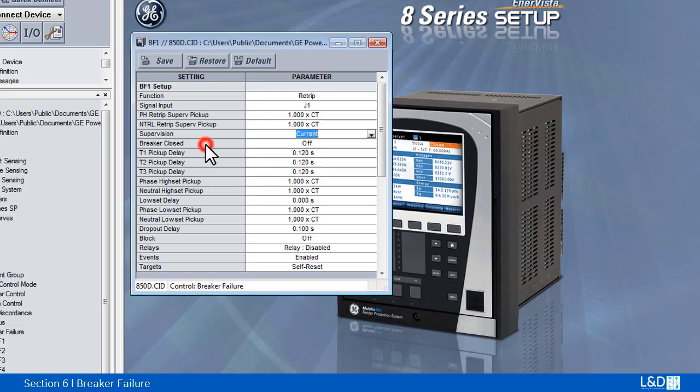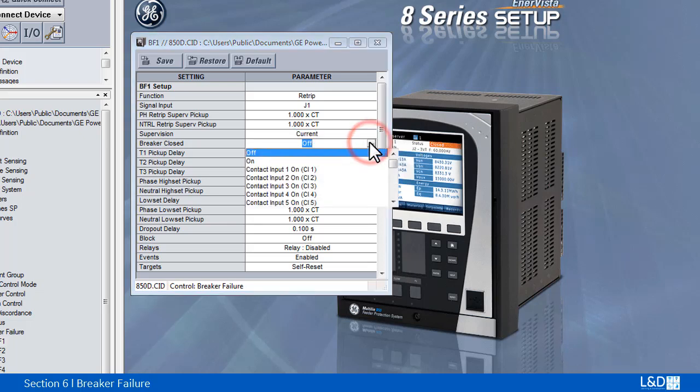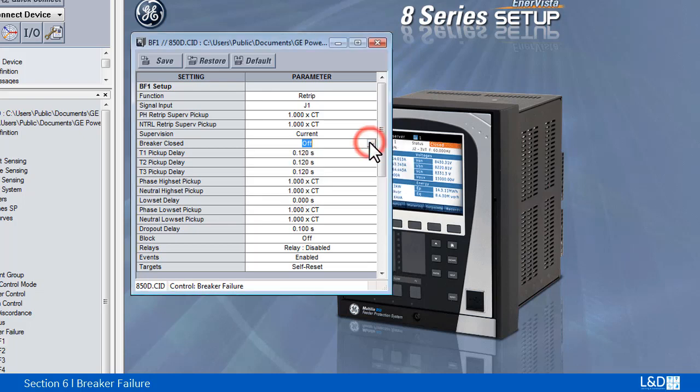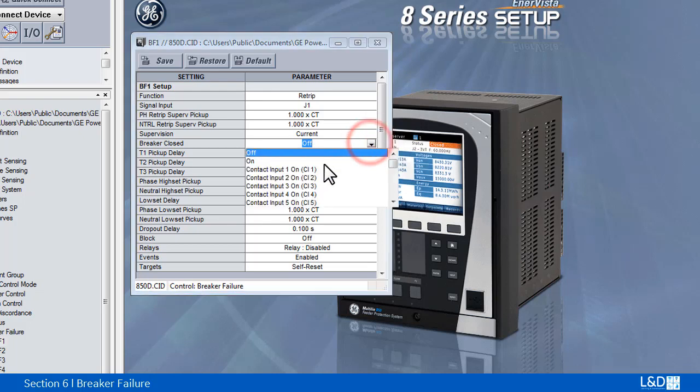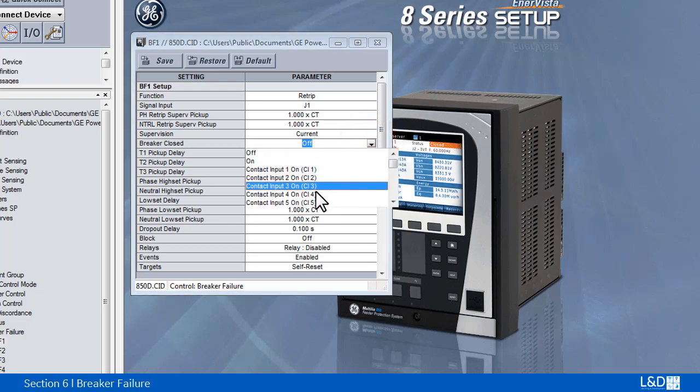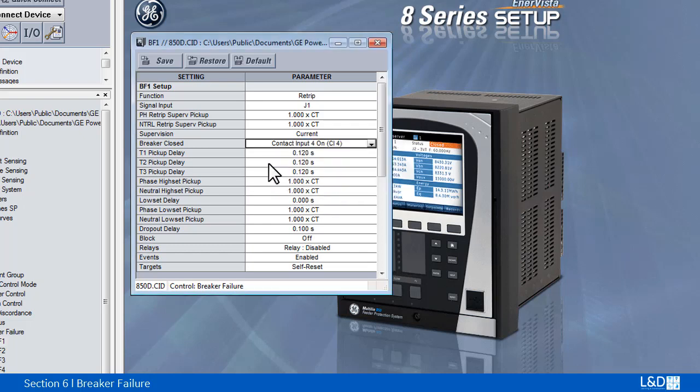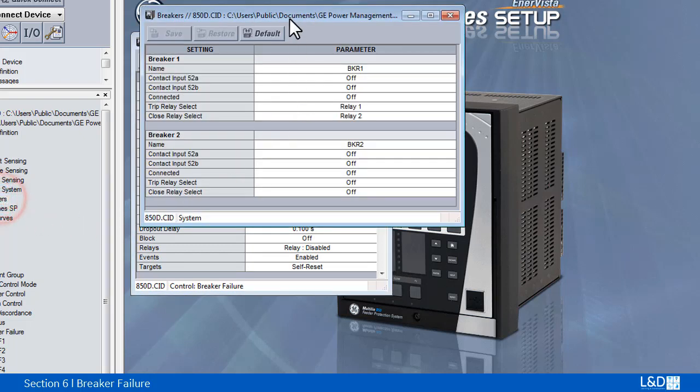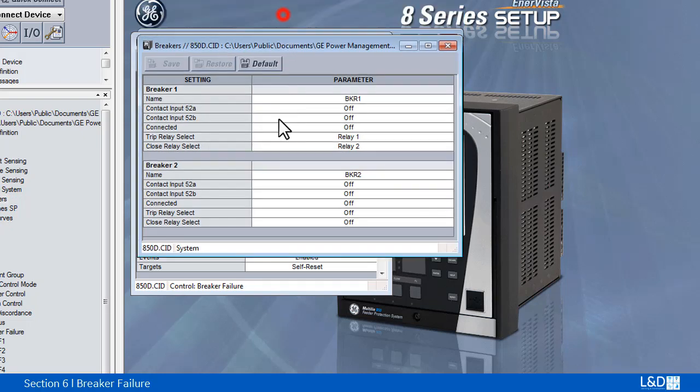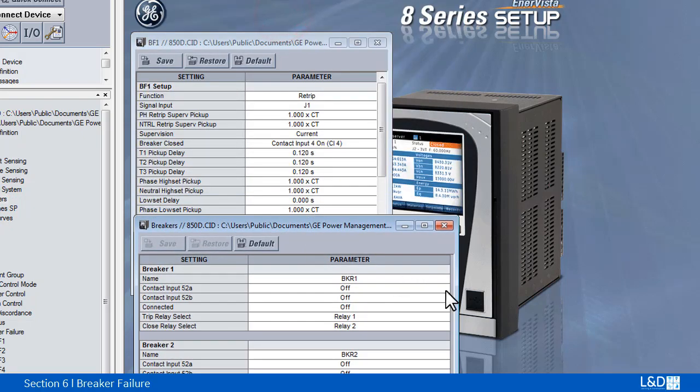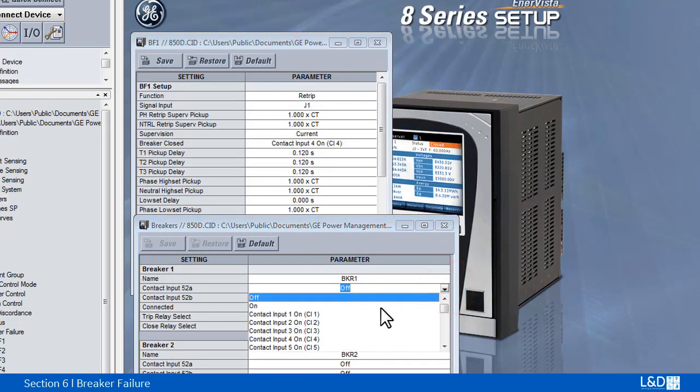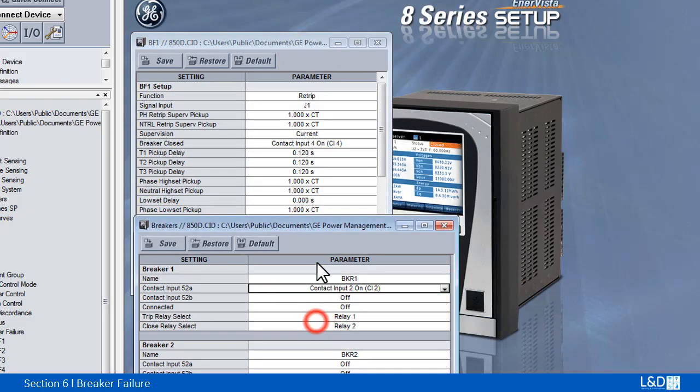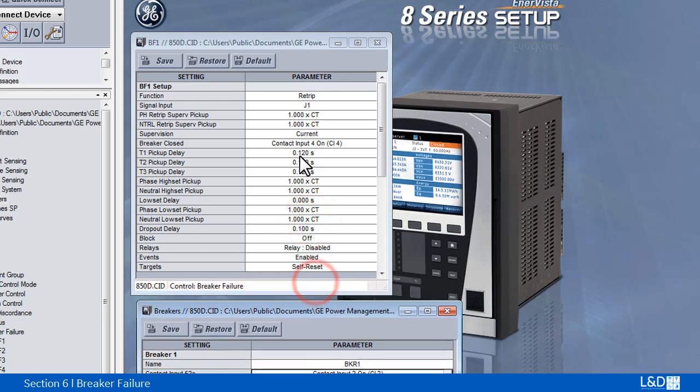Breaker closed selects the flex operand to indicate that the circuit breaker is closed. When there is a conflict between this breaker closed setting and the setting of the breaker under system, the setting in breaker failure's breaker closed prevails.